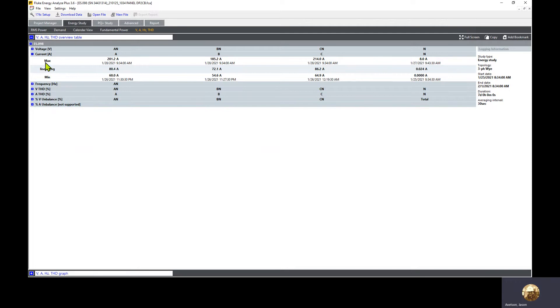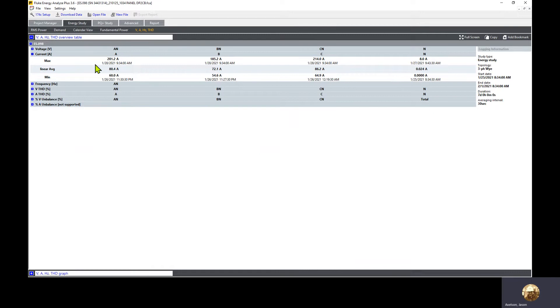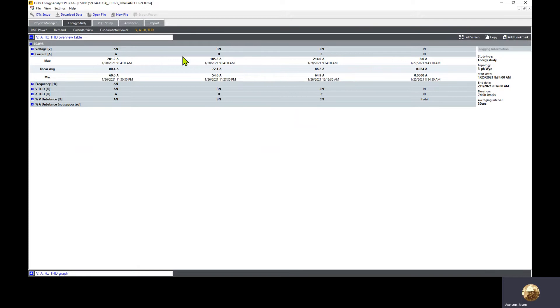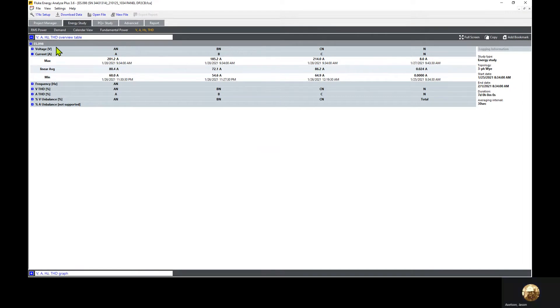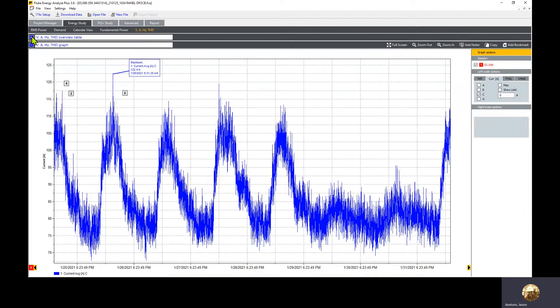We see max, average, and min. The maximum here is much higher because we're just looking at the half cycle maximum, which isn't what we want. If you still want to incorporate the highest, lowest, and average measurements into the report, we could click add bookmark to add this. But it can be a little deceptive because this is not the highest average. I'm not going to do that in this example.